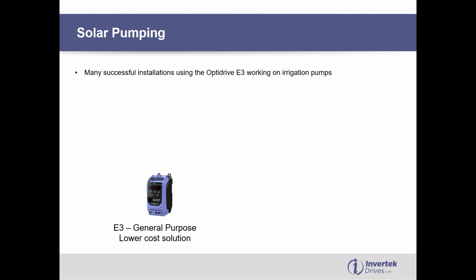We can do this with the E3 as standard, so it's an ideal solution for a low cost general purpose type solution. So instead of feeding the mains power into terminals L1 and L2 on the drive, you actually feed plus minus DC from your solar array.